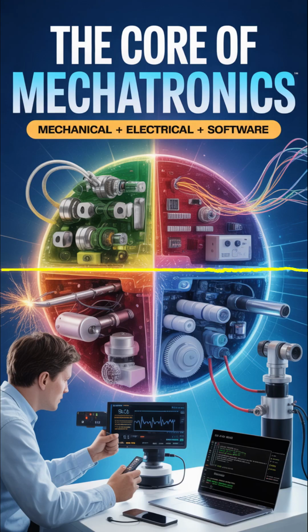Which brings us to the final crucial step, commissioning. This is the handoff, the whole cycle of testing, validating, running, and then finally handing the system over to the customer. And it requires technical skill and, honestly, an equal amount of people skills. The first job is just verifying the installation quality. You check that all the remote I/O devices are installed correctly. Is the earthing right? Everything has to be physically sound before you even think about powering it on. And what's the one checklist item that gets overlooked but causes all those weird noise problems? Verifying the earthing integrity across the whole facility. If you have ground loops or poor bonding, you're going to get noise in your signals. So before startup, you have to check that the earth connections are solid and give you a clean, zero-noise reference point.